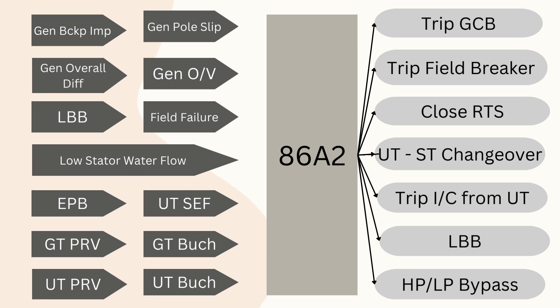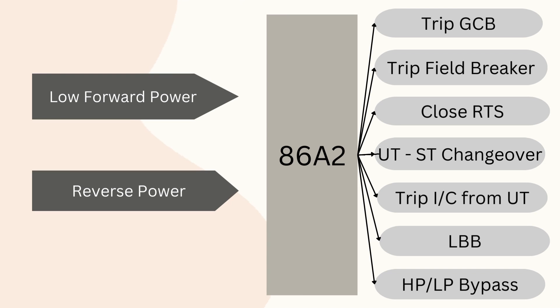Class A2 protection is similar, covering other generator-related protections and a second set of protections. The pressure release valve, buchholz, and standby earth fault of both GT and UTs fall under this scheme. A second set of low forward power and reverse power protection is also provided to increase reliability.